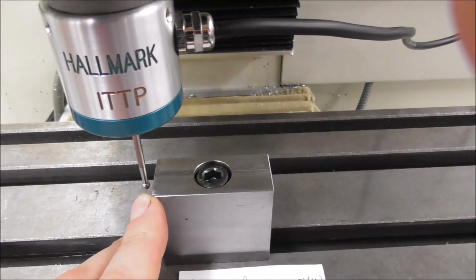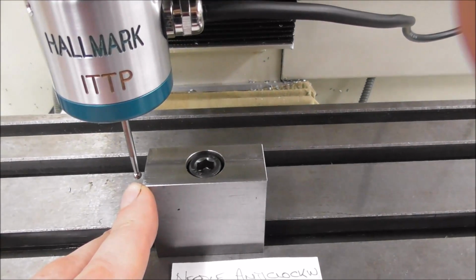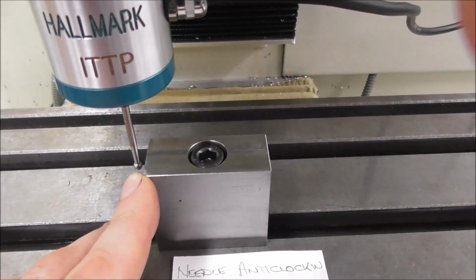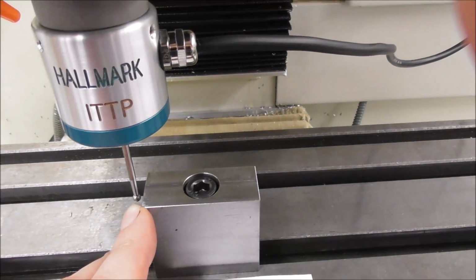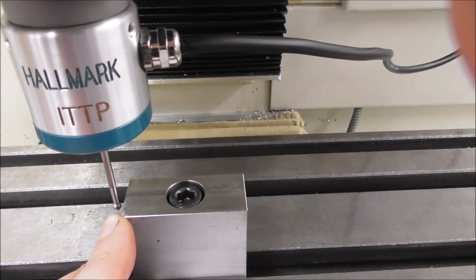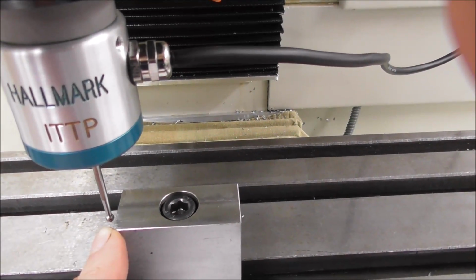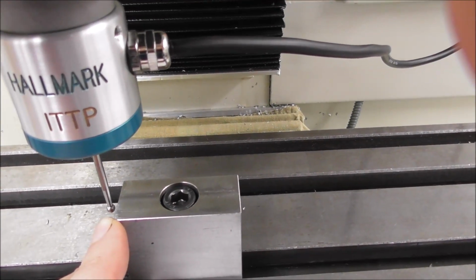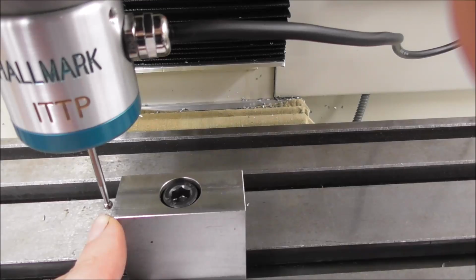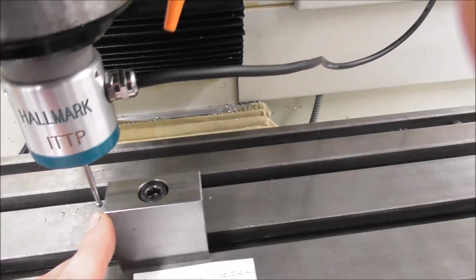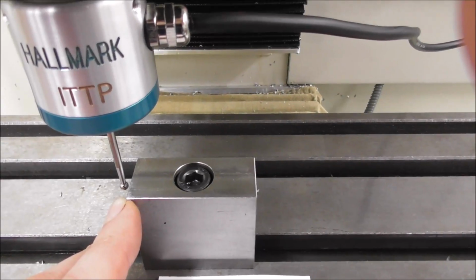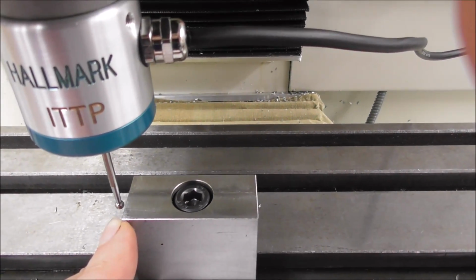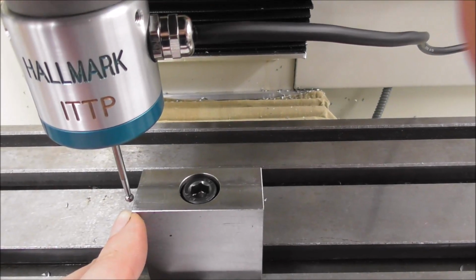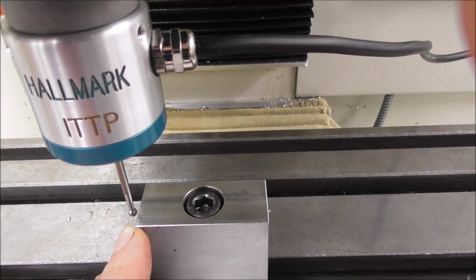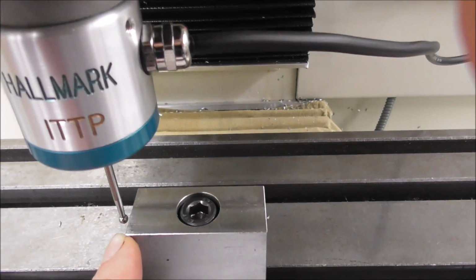Once you've set the stylus tip concentric, now it's a good time to set in the tool table the stylus tip diameter. And if you measure the stylus tip diameter carefully with a micrometer, you would think you'd just put that into the tool table so the software can do the maths and work out the radius and where the center line is. But it's not quite that simple. We have 2 factors called pre-travel and pre-travel variation that need to be factored in, that need to be understood. I'll just talk about it very briefly here because it's a big subject.